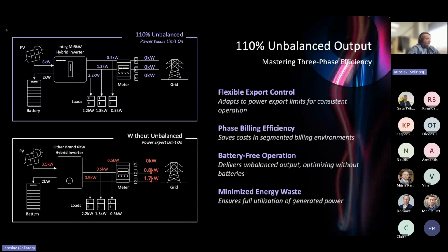In case you have another brand of hybrid inverter which doesn't have unbalanced output, you again cannot export any energy. On phase 1, you have a consumption of 0.5 kilowatts, the same scenario. When you have on the second phase a consumption of 1.3 and on the third phase 2.2 kilowatts, you see you have to buy electricity from the grid: 0.8 kilowatts on the second phase and 1.7 kilowatts on the third phase. That means you have not optimal usage of the energy in this case.